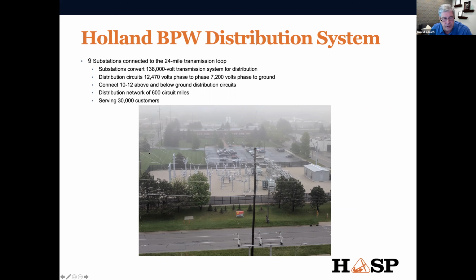Here you see the 3 phases coming in from the loop, through these circuit breakers and switchgear, and also going back out to the loop to continue on, through various switchgear and circuit breakers. You see these 2 transformers - this is a very standard setup, all their substations look the same. Then there's a setup here where each of the circuits exits the station.